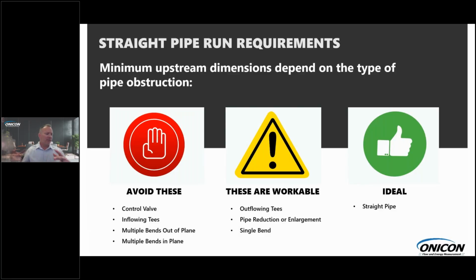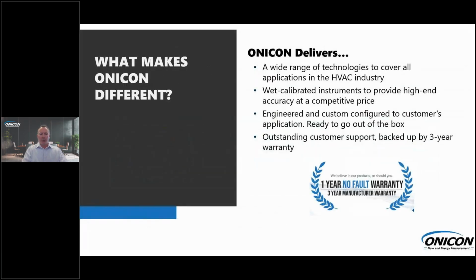And why we mention that is, we've had run-in scenarios. If you think about a closed loop system, everyone's always so focused on the supply side, not even taking into account the return side, where if it's a closed loop system, you should have that same flow rate on both sides. So definitely there's ways that we can work with you to find the best location for our insertion flow meters. And now it'll be back to Mike.